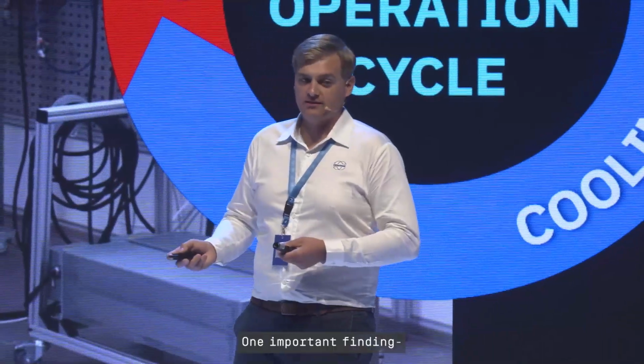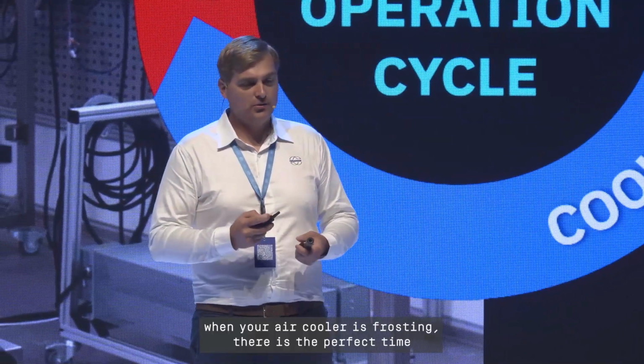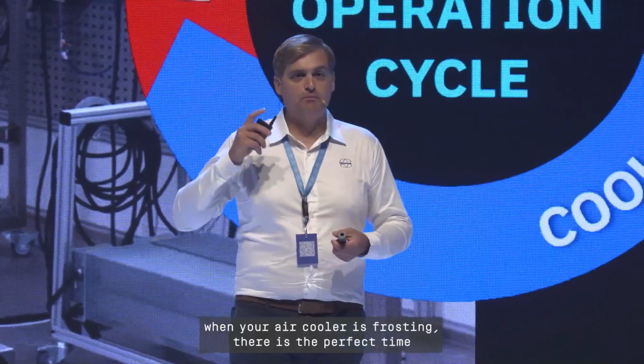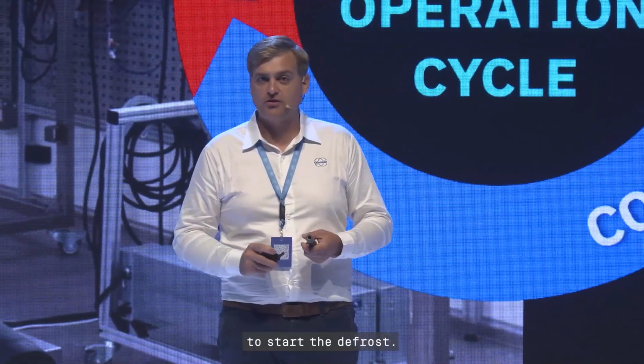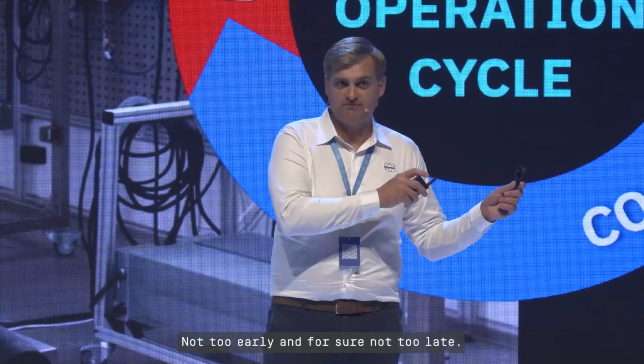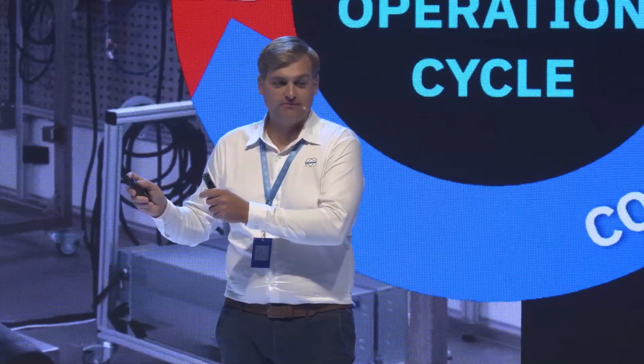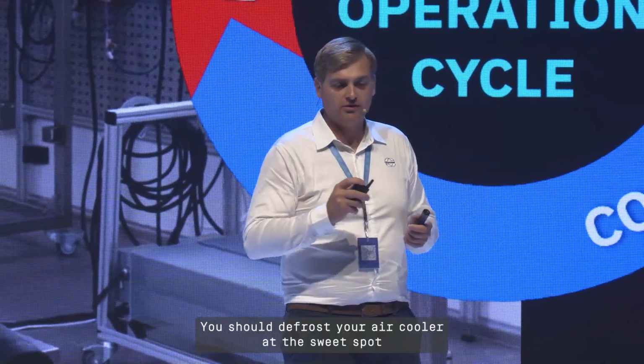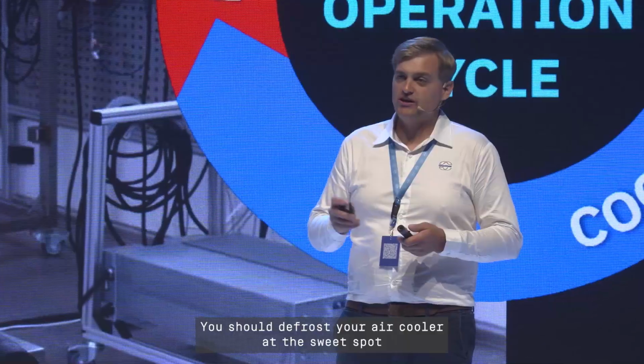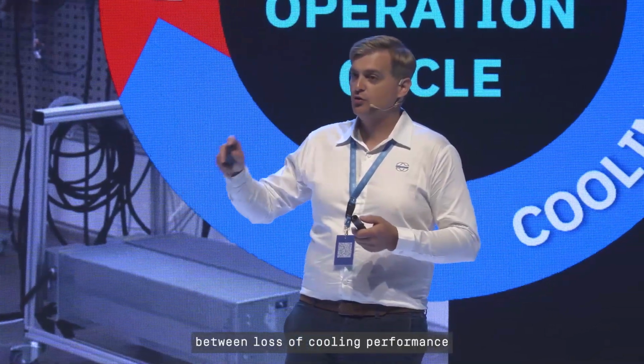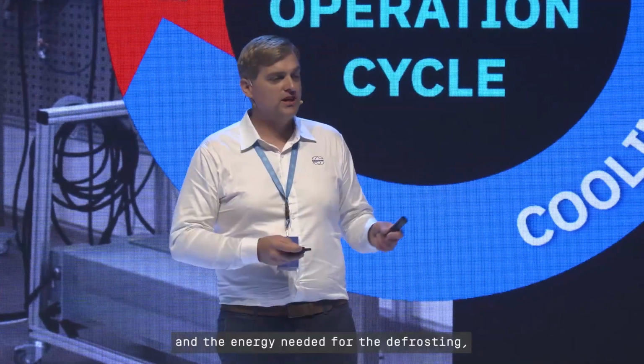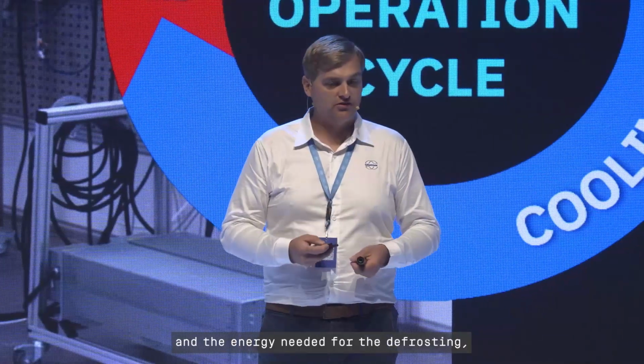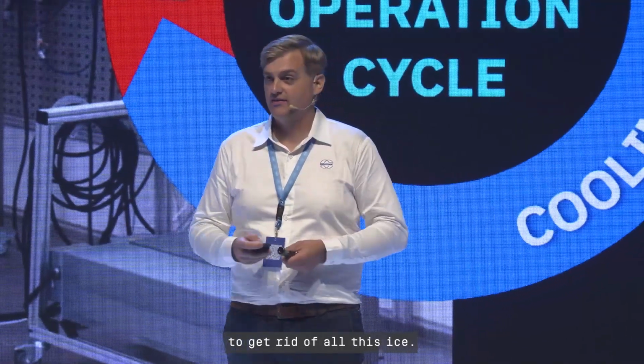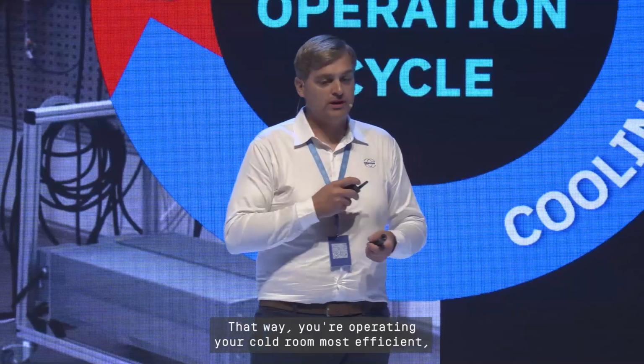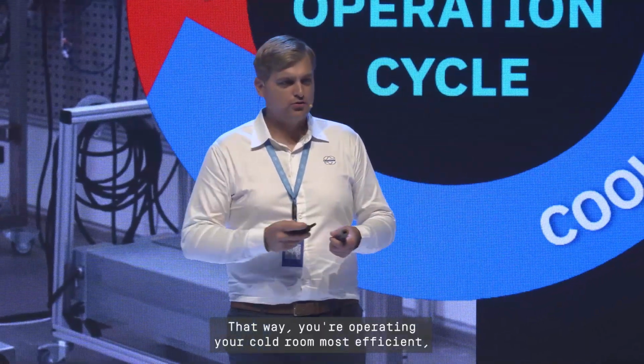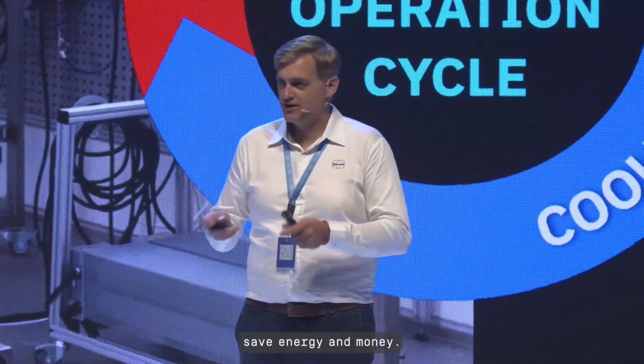One important finding: when your air cooler is frosting, there is a perfect time to start the defrost - not too early, and for sure not too late. You should defrost your air cooler at the sweet spot between loss of cooling performance and the energy needed for defrosting to get rid of all the ice. That way, you're operating your cold room most efficiently, saving energy and money.